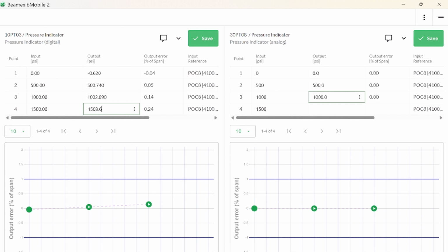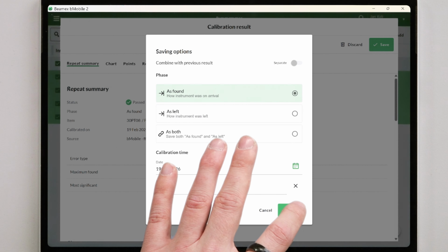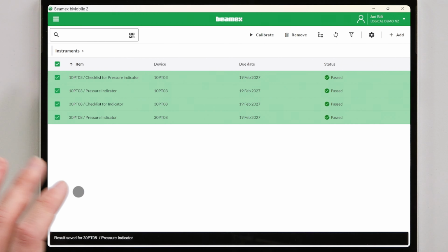And in here you can check the results, see if there are any result notes that you want to add to the result itself. Check the graph, everything looks fine. I'll click on save. I'll do an as found calibration, save, and then one more time for the other indicator. As found calibration, save, good.